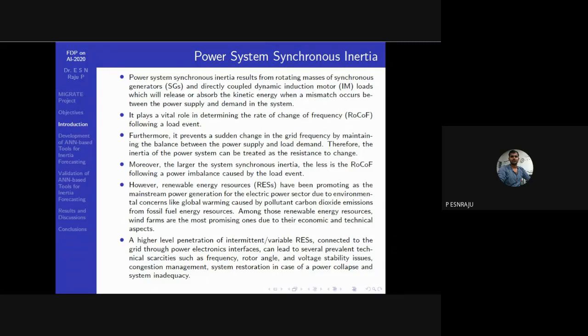Power system synchronous inertia mainly results from the rotating masses of synchronous generators or directly coupled induction motor loads. This will mainly release or absorb kinetic energy when there is a mismatch between power supply and demand in the system. It plays an important role in determining the rate of change of frequency.